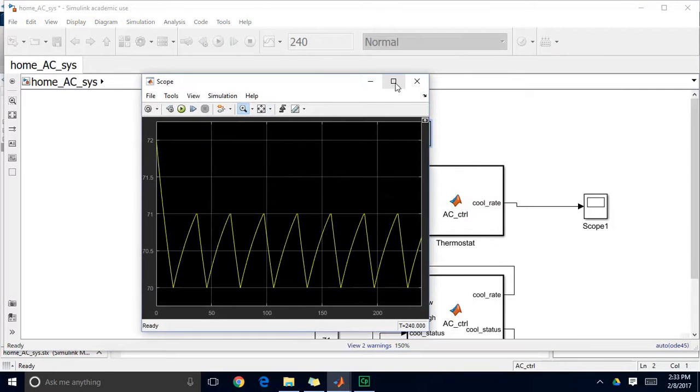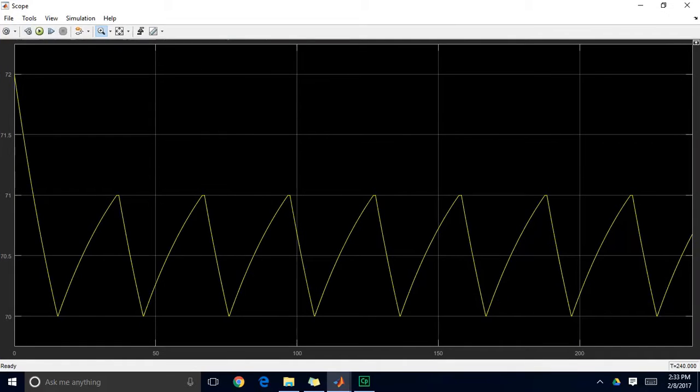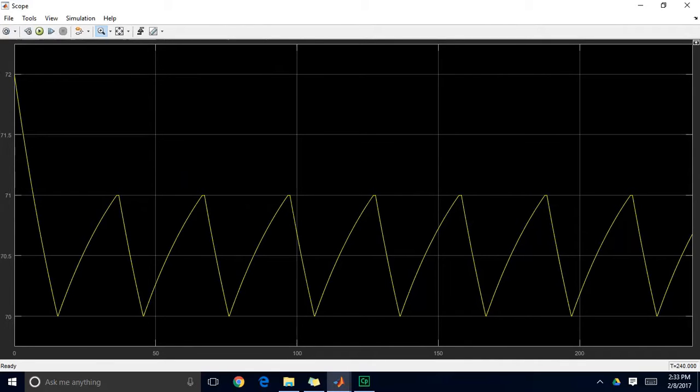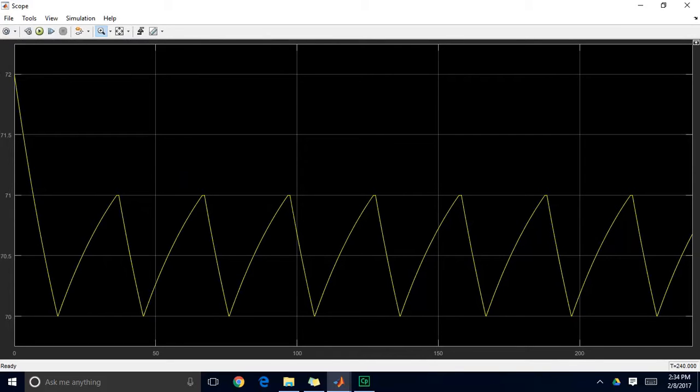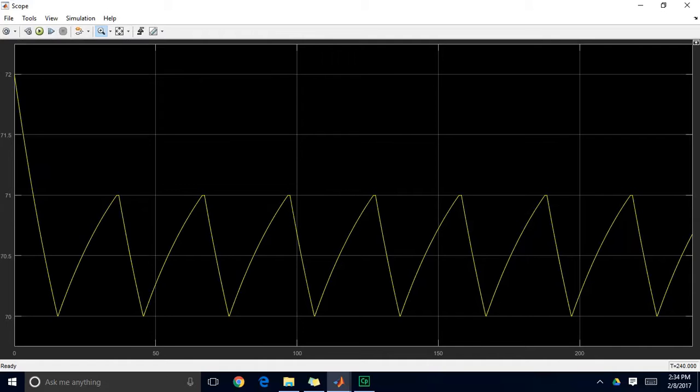So you can see this is performing just very much like the way your home air conditioning system works. We cool from 72 down to our low setpoint, at which point the cooling status changes from 1 to 0. So we turn off our cooling system. That allows the temperature in the home to rise. When it reaches the high setpoint, then we change that cooling status back to 1 and we cool down to our low setpoint. So you can see we're still getting this oscillation in our system, but our temperature is basically floating between this dead band of 70 and 71.